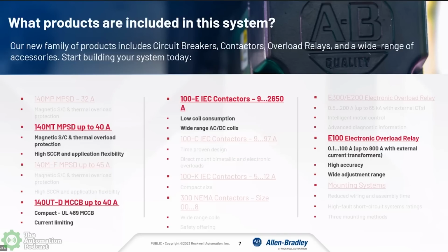And then finally, our E100 electronic overload relay. This provides that longer term thermal protection of a motor historically. It's an electronic overload relay with a wide current adjustment range, with wide capability ranges as well if you add some external current transformers. We've got a couple different versions, but one of the things I highlighted was the direct connect abilities. We offer the E100 overload relay with, from the factory, direct connect capability into our 100E contactors. We also offer that into our 100C contactors, which have been out in the market for a while.